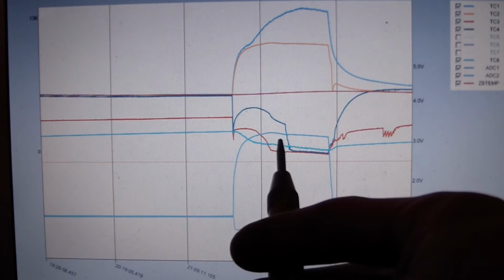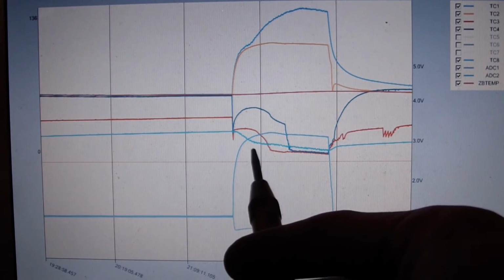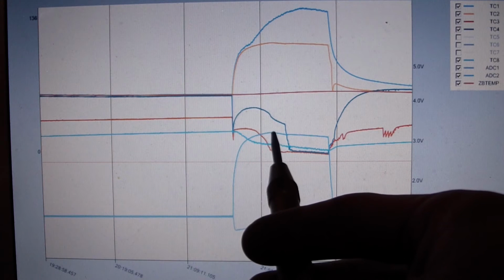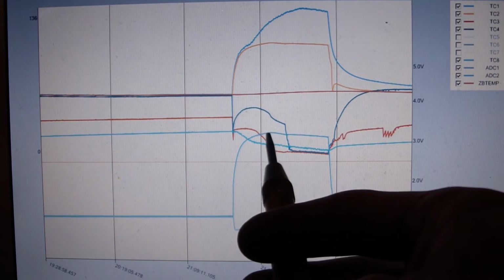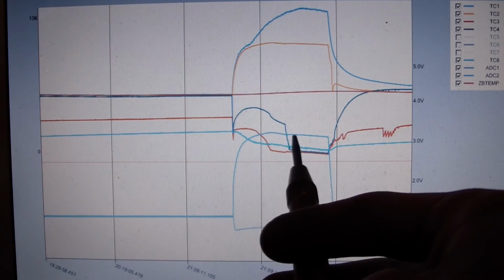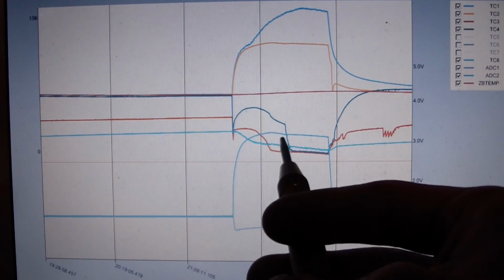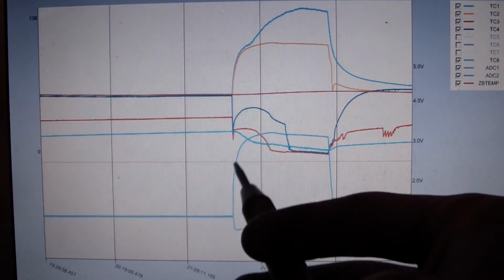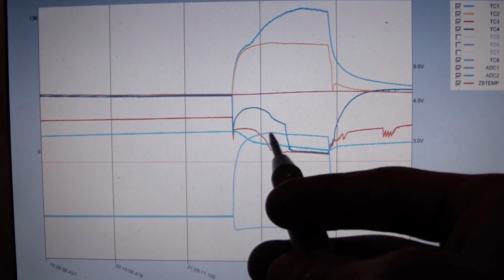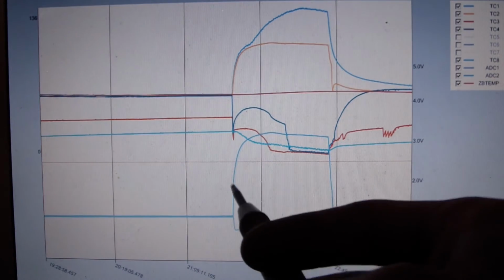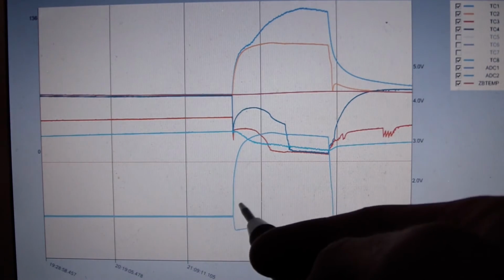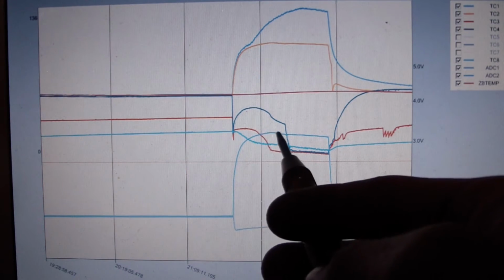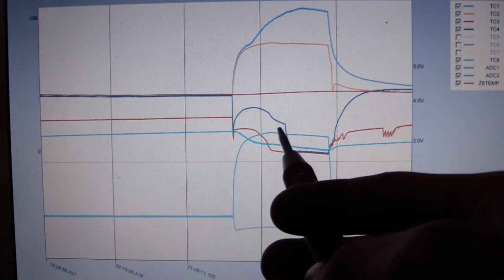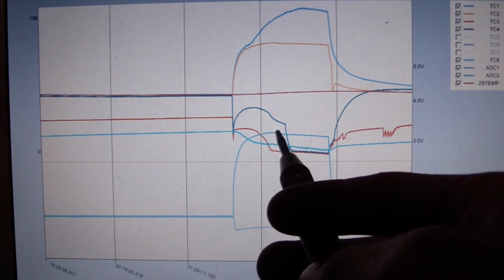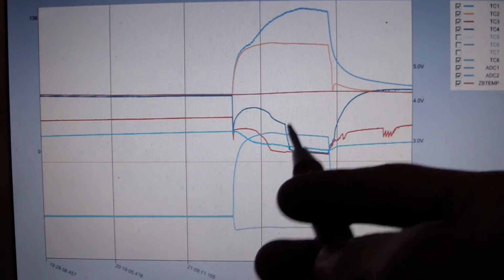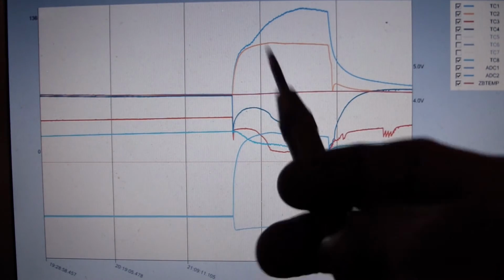Another interesting point to talk about here is the peak of the pressure on the high side. That seems to occur at an interesting point where it finally peaks and then it drops off and slowly drops over time. All this time, from the beginning of the startup until probably about that point, we were getting plenty of back pressure from the gas that's trying to pass through the capillary tube. Somewhere in here we're getting pretty good flow, and that's allowing more mass to flow through the capillary tube and relieve some of that high side pressure.